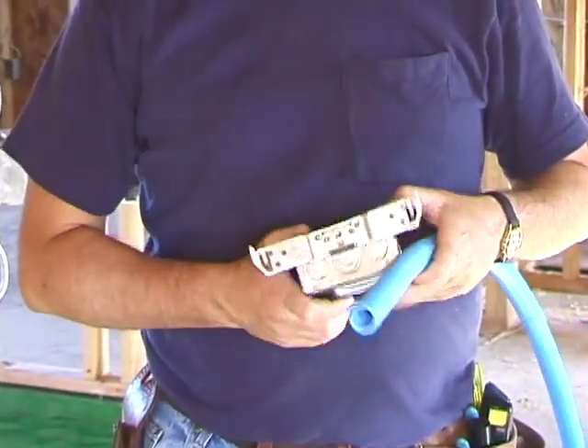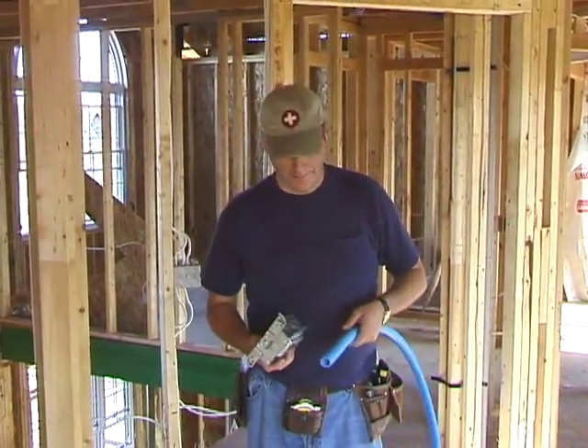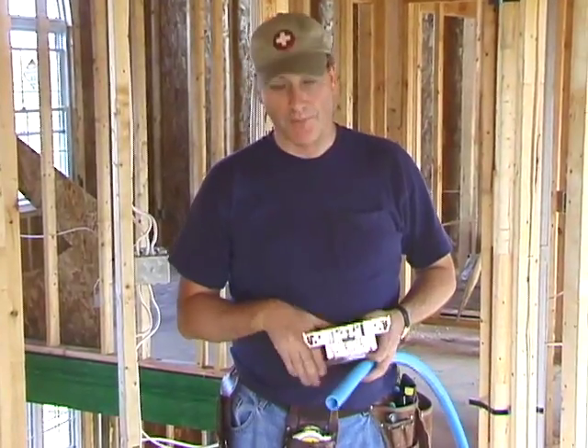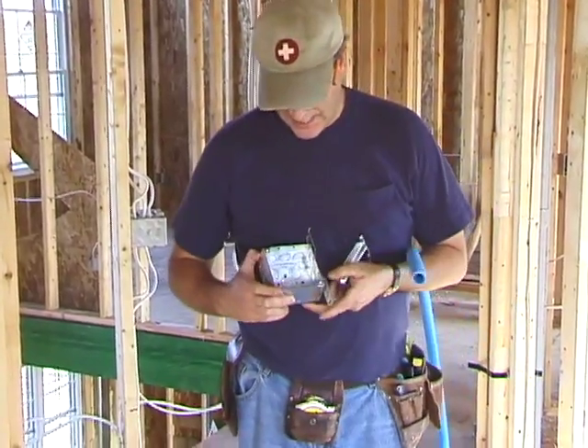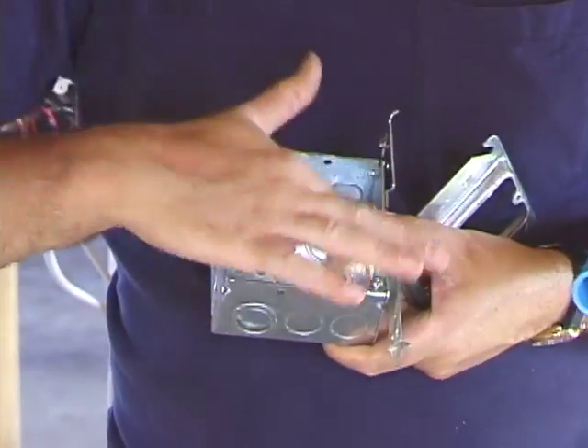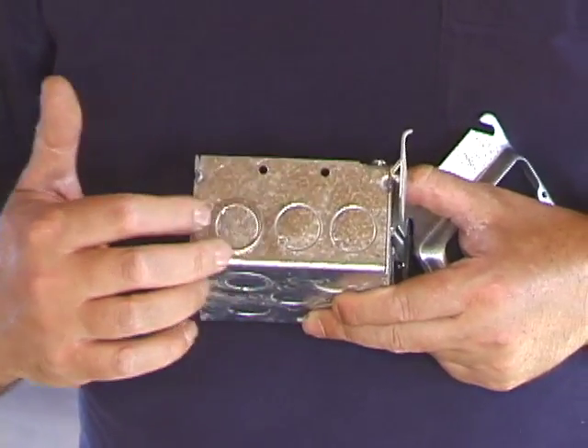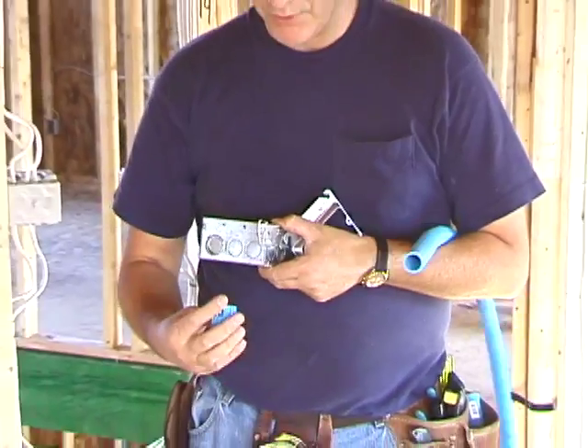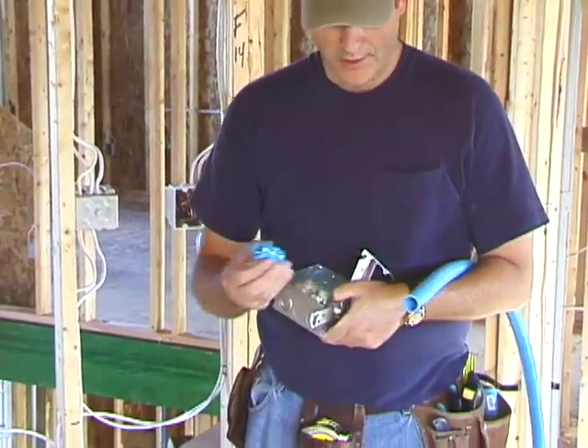As long as you don't get too aggressive with the bends, you'll be able to fish a tape through later. We're not putting the wire in until after the drywall — we don't want to hold the drywall people up, and we want a nice clean finish. We also have a 4-inch by 4-inch box that we picked specifically because it's very deep — we're terminating Cat5 and doing all kinds of wiring in here. We picked it because it has a 3/4-inch opening, rather than the standard half-inch, so we can put quite a few wires in.